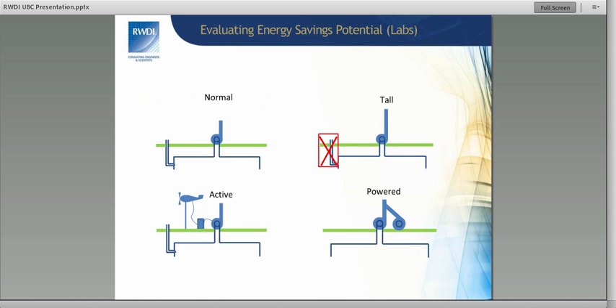So there's 4 basic types of ways we can do it. One is the normal way. We've designed our stack, we've done a good job, it works, we can turn it down, everything's safe, great, we can save energy that way. If it's not safe, one thing we can do is we can use something called bypass air. So usually what that means is you have a fan with a damper, and when you turn down the demand from the building, air is pulled in at the roof to keep that one big fan going at a high rate. And so whatever we've put in through the fume hoods is still being diluted and pushed out by a nominal airflow at the fan. So there's one thing to have a bunch of small fume hoods connected together, but what you're really interested in is what is that total airflow rate at the fan.